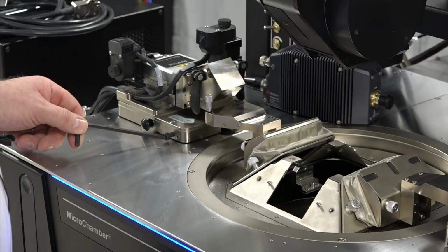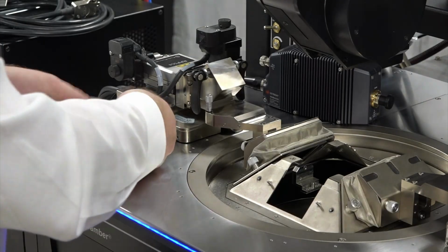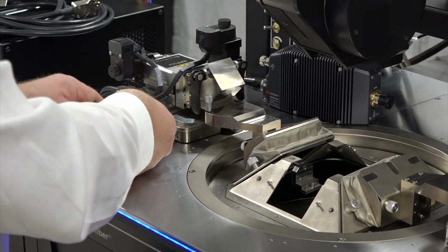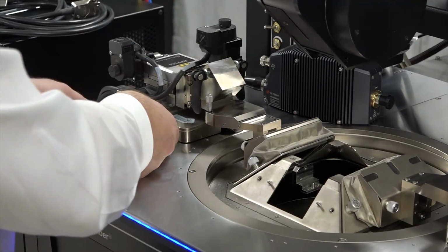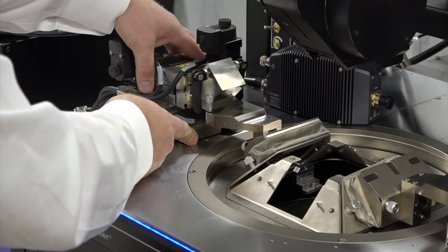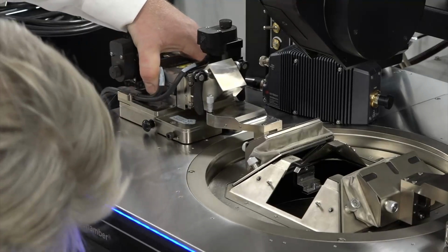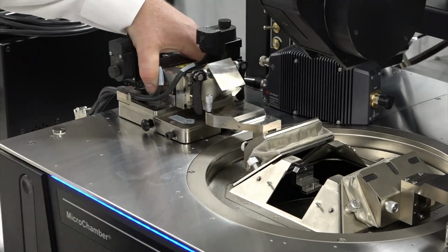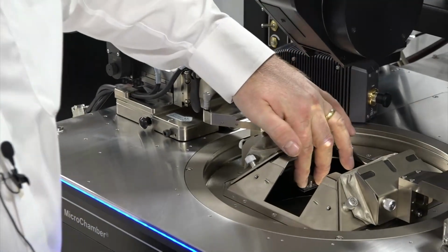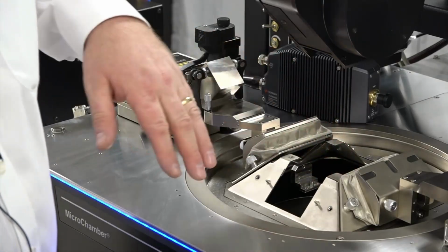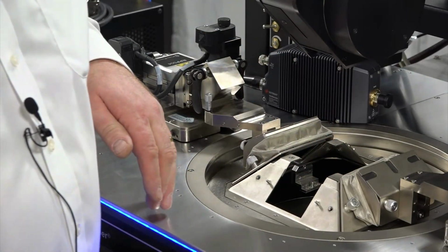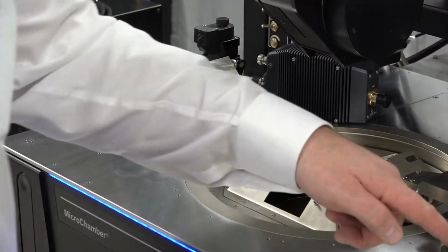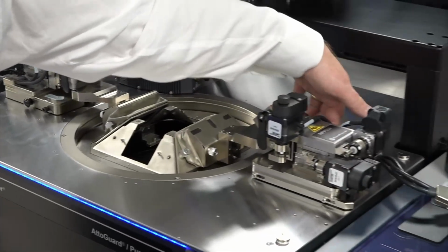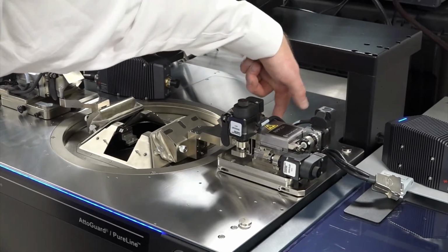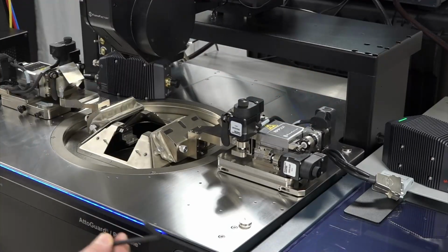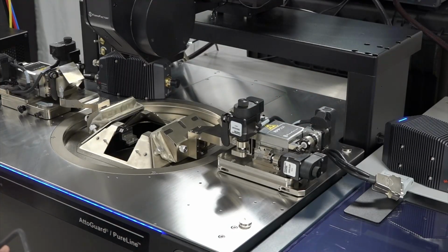Prior to putting any weight on it, what I will do is I'll just put these screws in, just in case, most of the way in, but not tight, just enough so they can still move. Because I'm going to put my probes on there and look at the shadow of the probes, just to check the position of my bases. Similarly on this side, the screw for this side is around where I'm pointing, just back here. In order to tighten this, you'll need a 5mm Allen wrench.